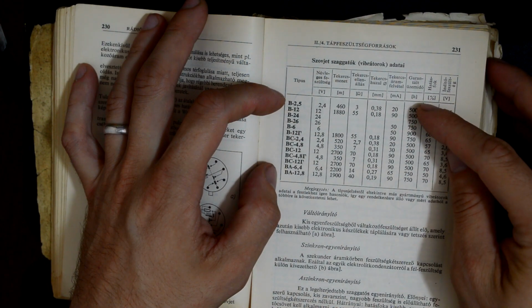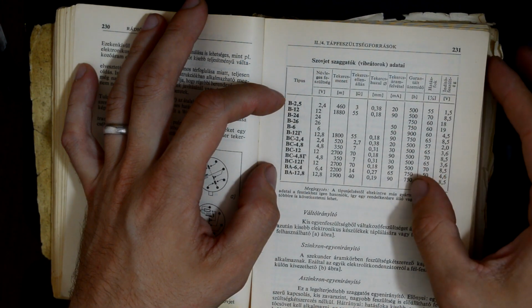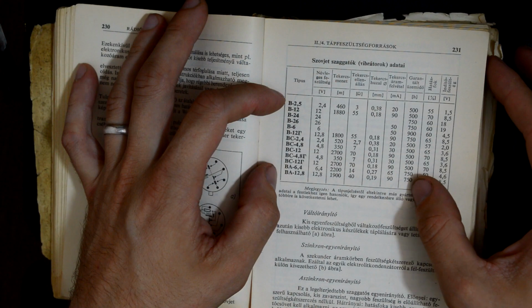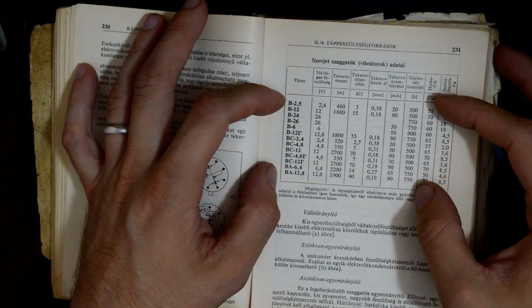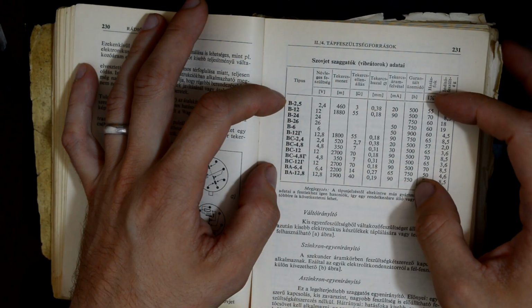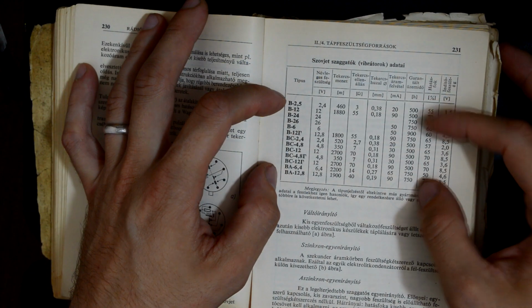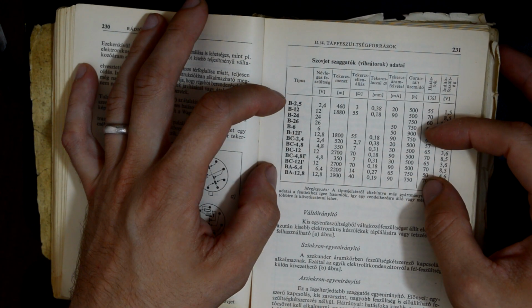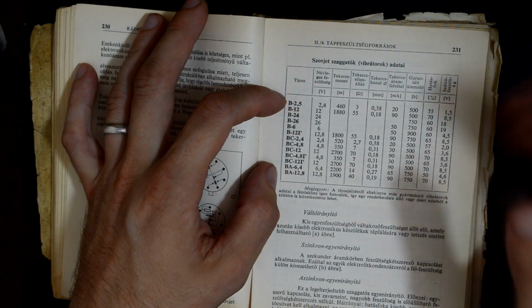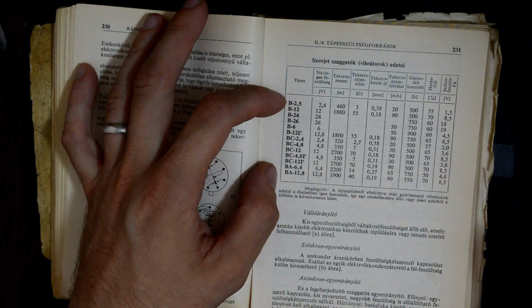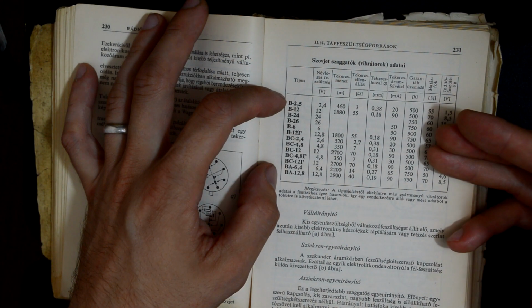The next parameter is how much time this thing is guaranteed to work, and we can see that this sort of mechanical vibrator can work between 500 and 900 hours. Now, a typical vacuum tube has around 5,000 hours of lifespan, and modern semiconductors have on the order of tens or hundreds of thousands of hours. This thing will break after 500 hours.